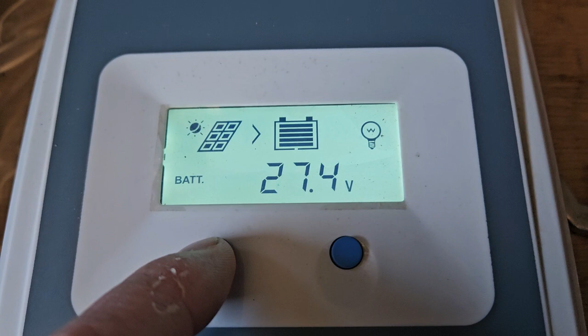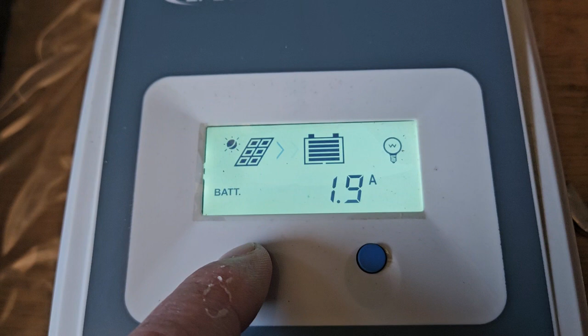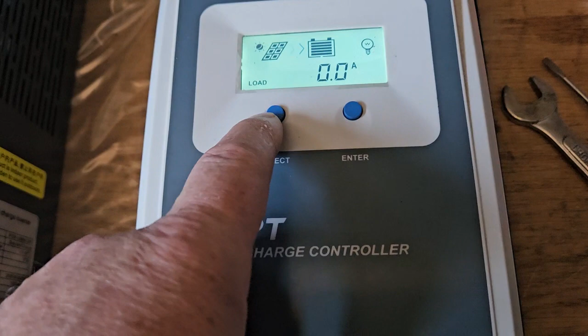It shows the voltage, how many amps going to the battery, and the temperature of the unit, or you can get the probe and put it here. This reads the temperature, you can extend that. For lead acid batteries, you put the probe by the battery and it will adjust its charging parameters based on the temperature of the battery.